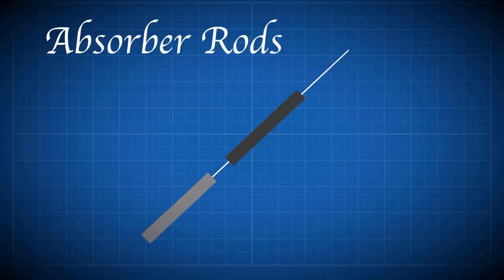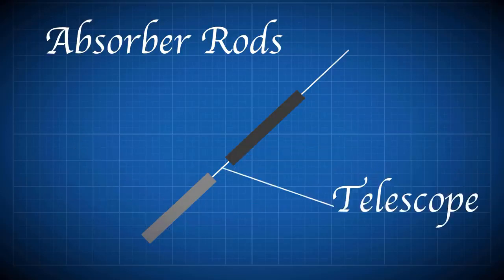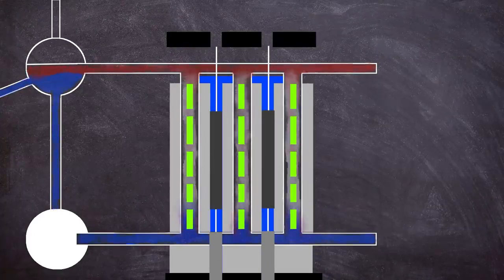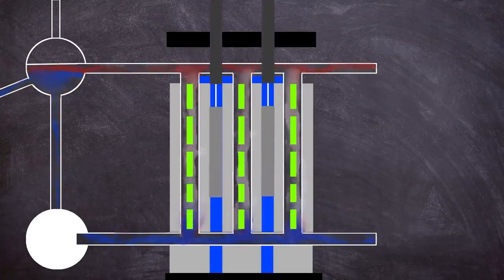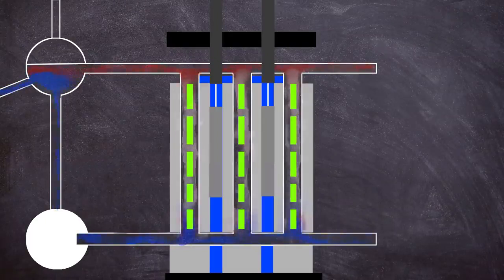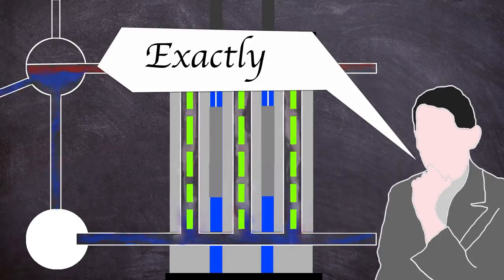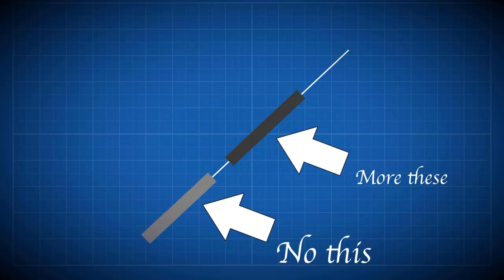The main control rods had a 4.5 meter long graphite rod termed a displacer attached to the end, except for the 12 automatic control rods. The displacer connected to its rod via a telescope with a water-filled space of 1.25 meters separating the displacer and absorbing rod. This was to stop water filling the space left by the control rod after it left the core region, which would parasitically absorb neutrons. Removing one neutron absorber in the form of a boron control rod to be replaced by another, weaker absorber in the form of H2O defeats the point. Thus if there was no displacer, more control rods would be needed as each would have less effect.